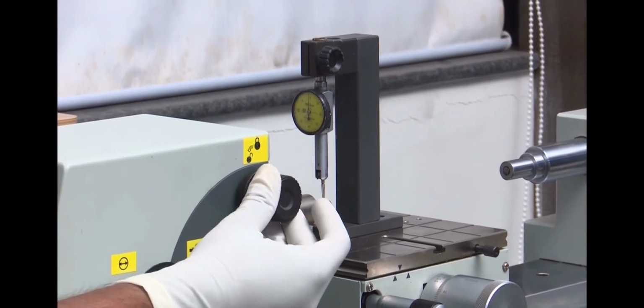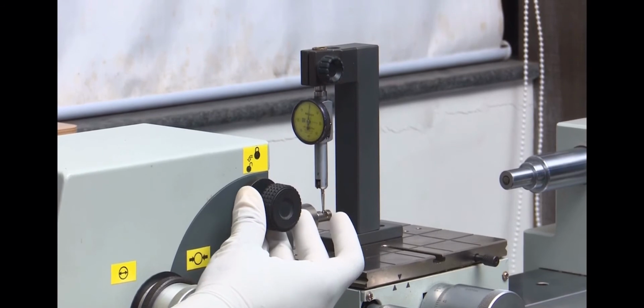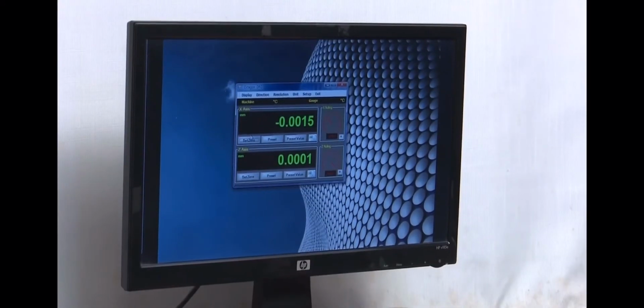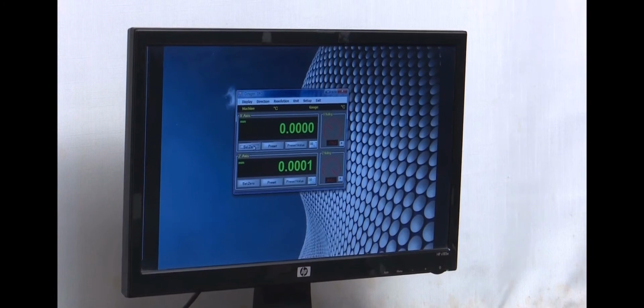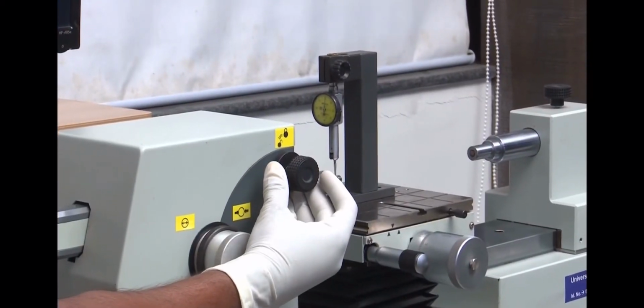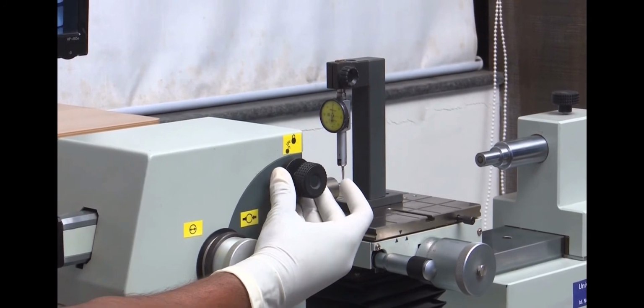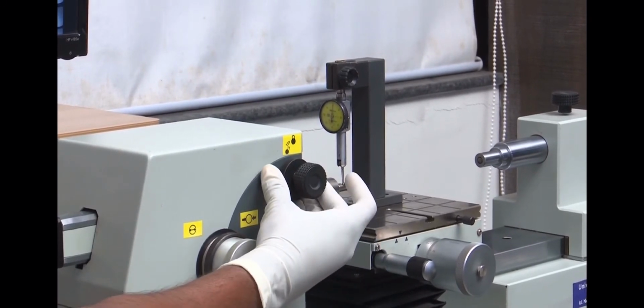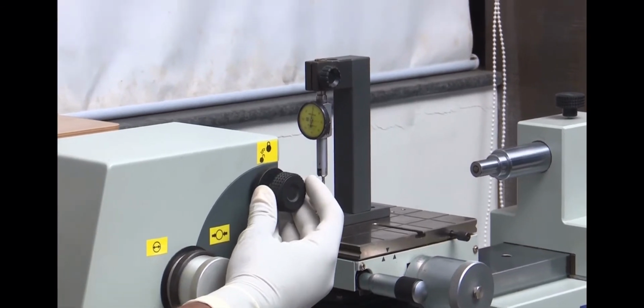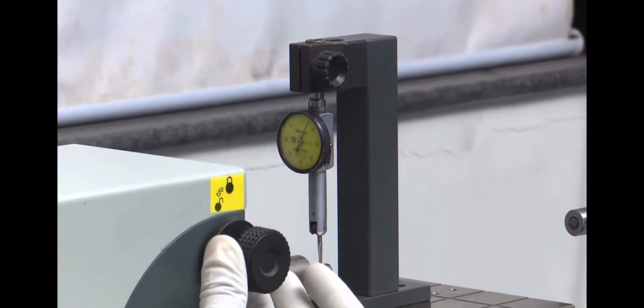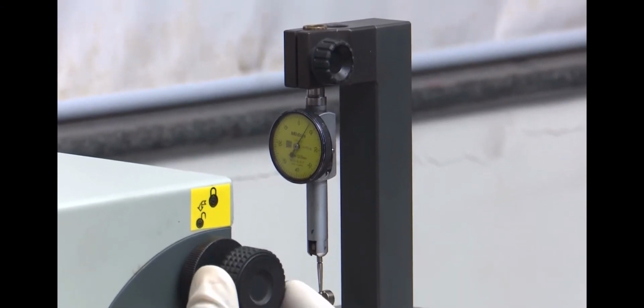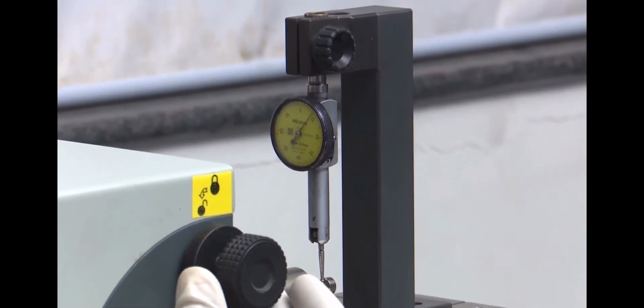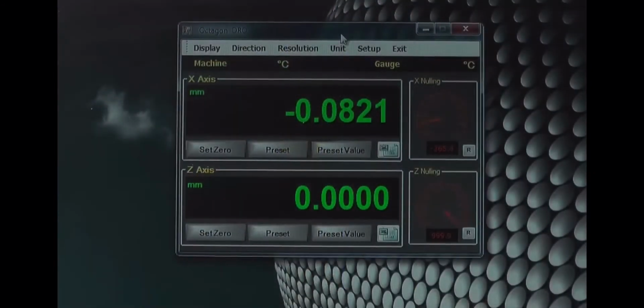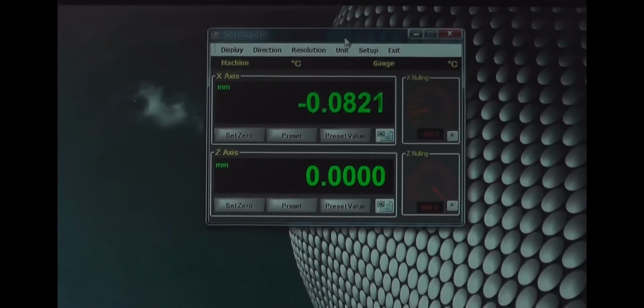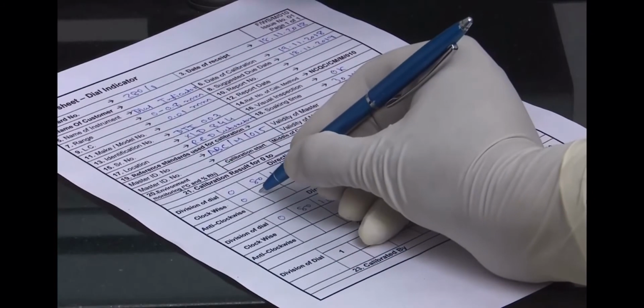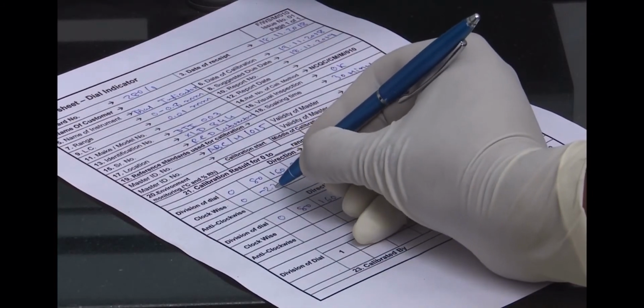Now I am applying pressure to the dial gauge till its pointer shows 0. Then I am setting x-axis display to 0. Here I am applying pressure on dial in clockwise direction by fine adjustment. Now set the reading on dial at 8 division, that means 0.08 mm or 80 micron. Calculate the deviation as dial reading minus display reading.